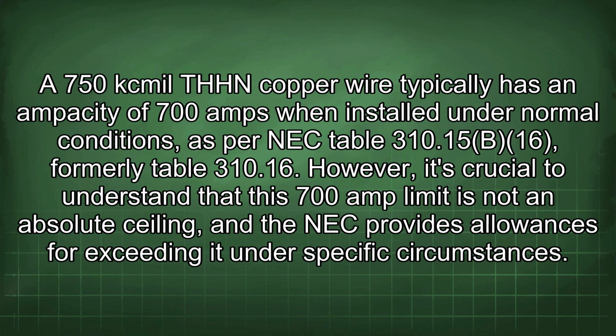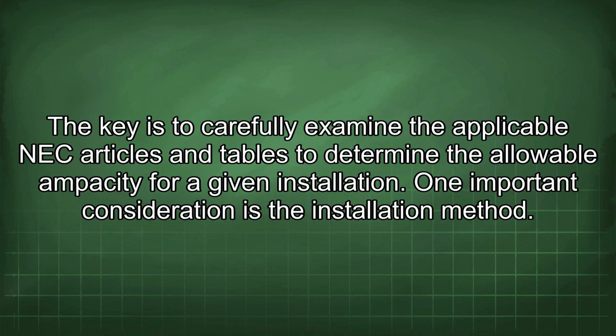as per NEC Table 310.15(B)(16), formerly Table 310.16. However, it's crucial to understand that the 700 amp limit is not an absolute ceiling, and the NEC provides allowances for exceeding it under specific circumstances. The key is to carefully examine the applicable NEC articles and tables to determine the allowable ampacity for a given installation. One important consideration is the installation method.